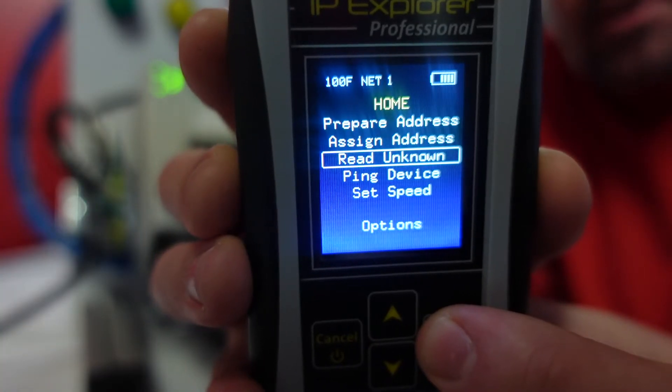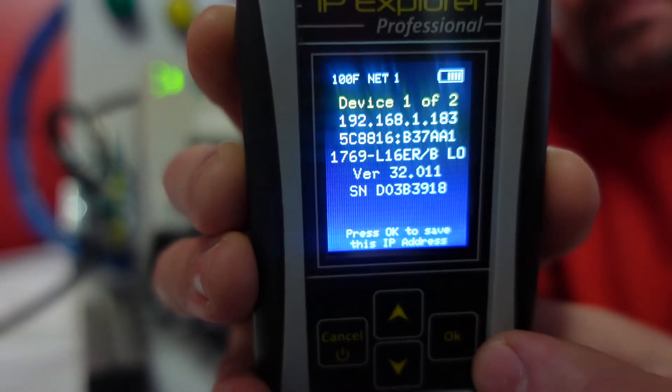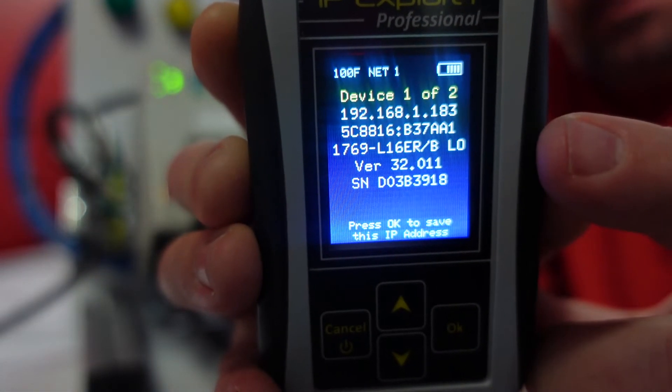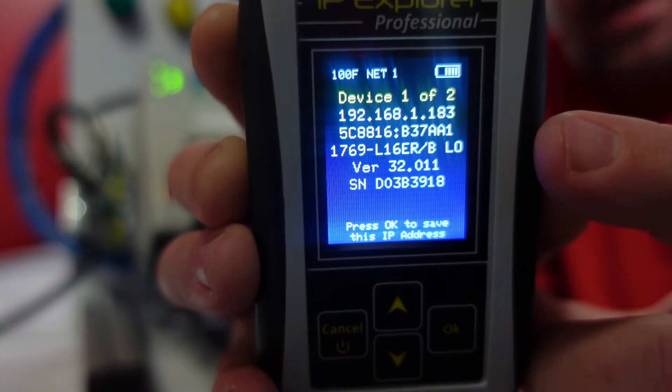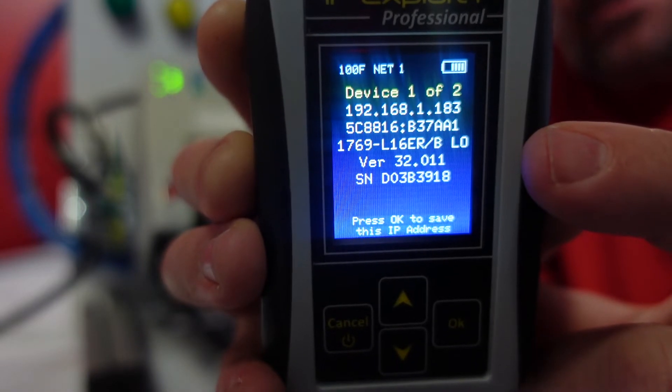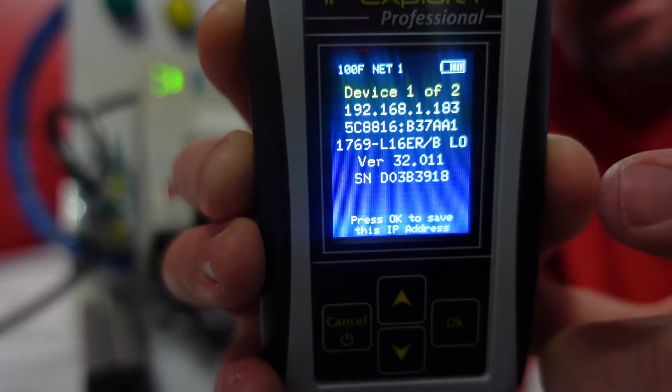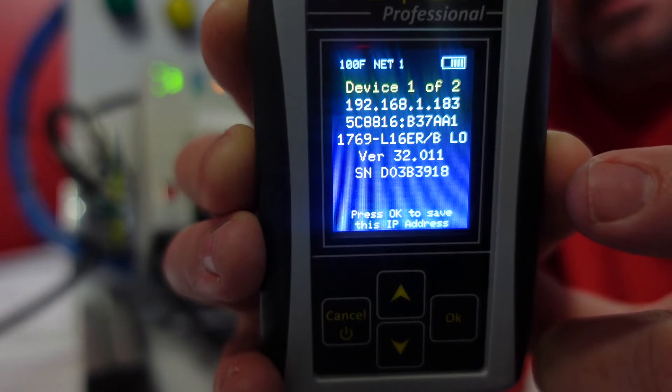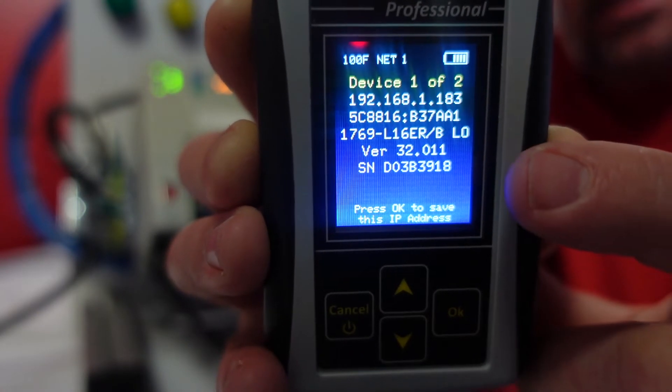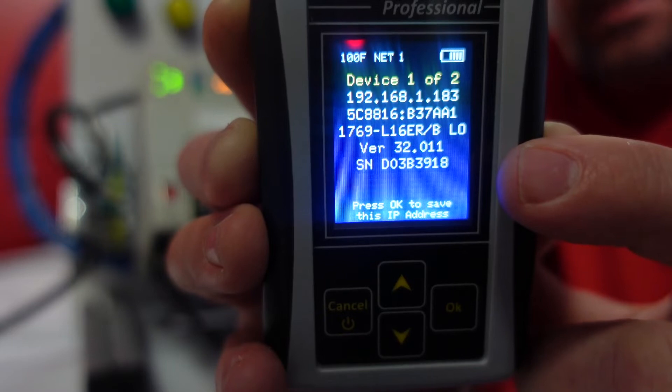From the main menu, I'm going to go to read unknown, and it's discovered two devices. This one's 192.168.1.183. It has its MAC address there, and most importantly, we have the model number. So I know this 1769L16 is that Compact Logix. It also tells us a version.